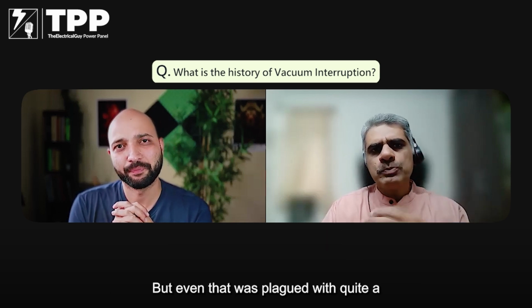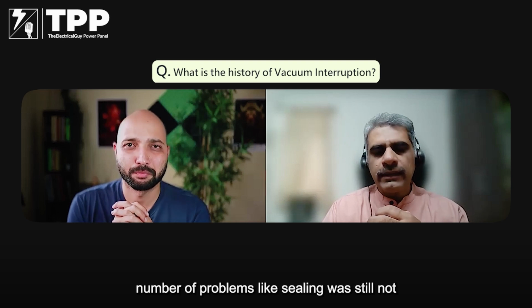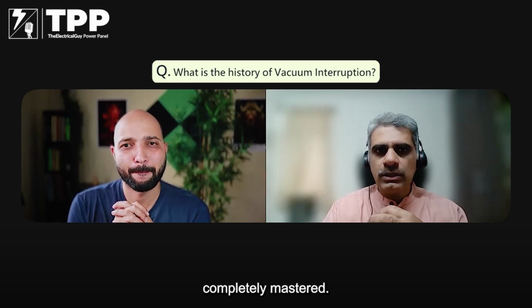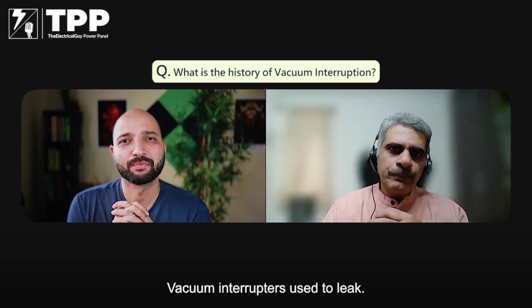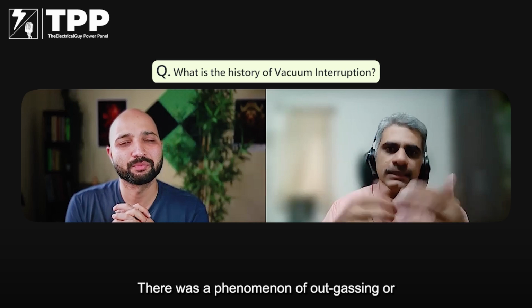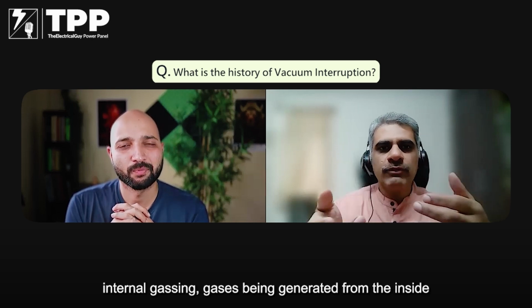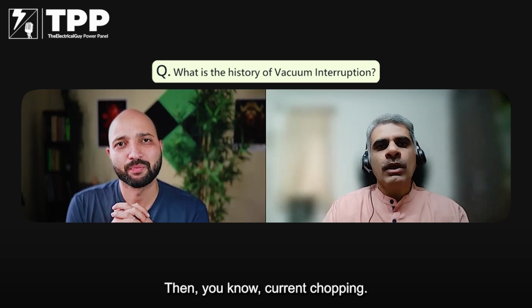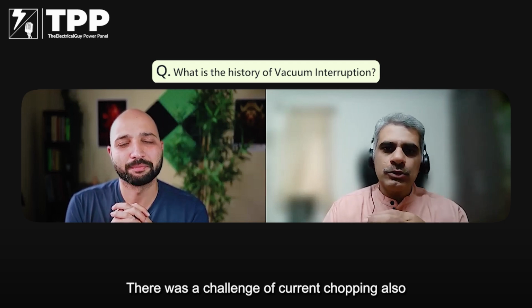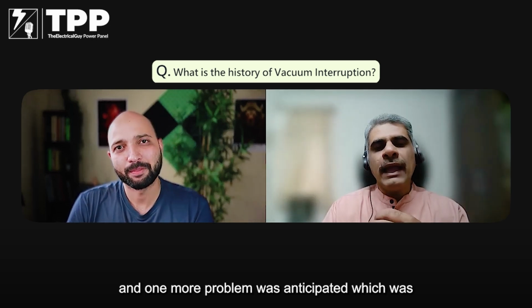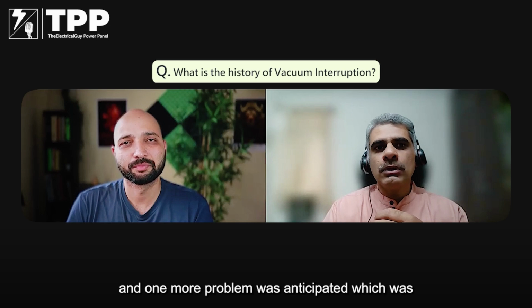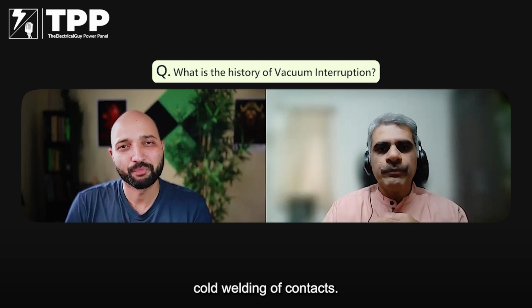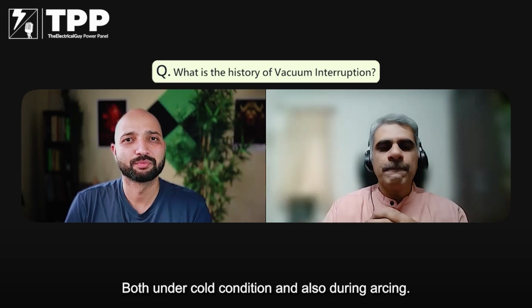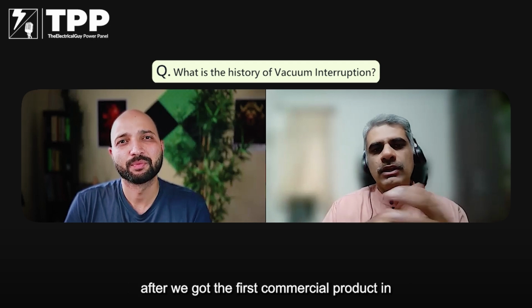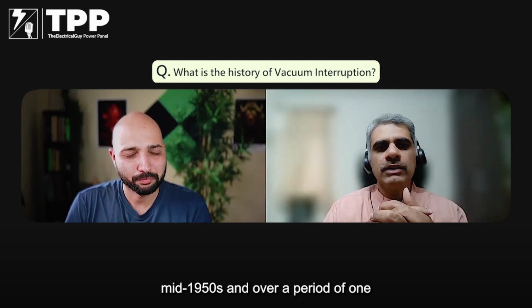But even that was plagued with quite a number of problems, like sealing was still not completely mastered. Vacuum interrupters used to leak. There was a phenomenon of outgassing or internal gassing, gases being generated from the inside components of the vacuum interrupter. Then current chopping. So there was a challenge of current chopping also. And one more problem was anticipated, which was cold welding, welding of contacts, both under cold condition and also during arcing. So there were, of course, many challenges even after we got the first commercial product in the mid 1950s.